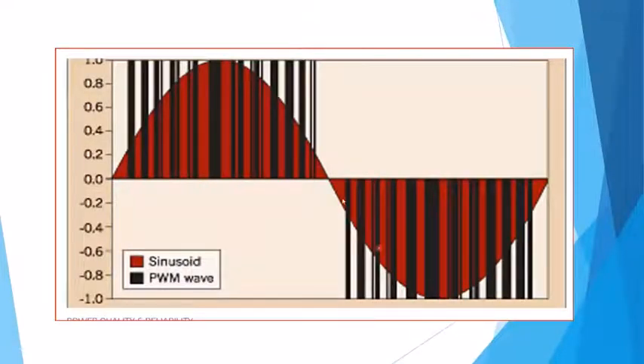So again, this is more of a look at the red, which is the actual current flow that's feeding out to the motor. So if you look down on the oscilloscope, you could actually see that this is more the sine wave. And what we're doing is we're controlling what we call the frequency here. So the faster or the slower, or the sooner we switch it from AC to DC, we can speed up the carrier frequency, or we can slow it down. So on some applications, if you have a pump or a motor that you're not quite producing enough, you can actually bring the frequency up from what its base frequency design was at, 60 hertz, you could bring it up to 61, 62, 63 hertz, and it'll actually speed it up and make the motor run faster.